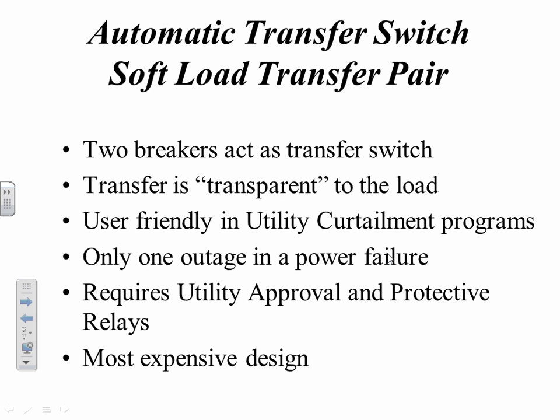Utility curtailment programs are set up to where there's an arrangement with the utility company. They come to the Target store and they say, look, you guys run that generator when we tell you to run it. It's usually on a hot day or a real cold day when they need more power. And we'll give you a 20% reduction in your power bill all year long. Good deal for the customer. He's just reduced his power bill by 20%. And typically, this curtailment period is going to happen only on hot days. Average has been 6 or 7 times in a summer, in a hot summer, when they've actually done that.